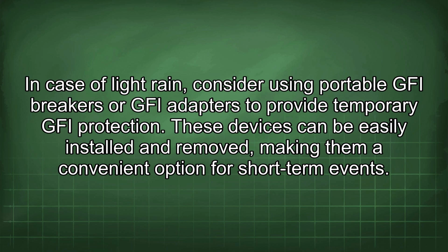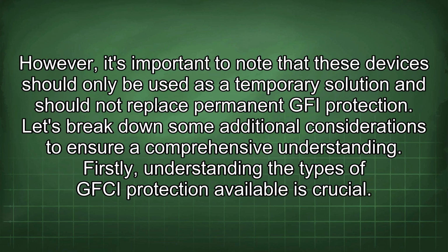In case of light rain, consider using portable GFI breakers or GFI adapters to provide temporary GFI protection. These devices can be easily installed and removed, making them a convenient option for short-term events. However, it's important to note that these devices should only be used as a temporary solution and should not replace permanent GFI protection. Let's break down some additional considerations to ensure a comprehensive understanding.